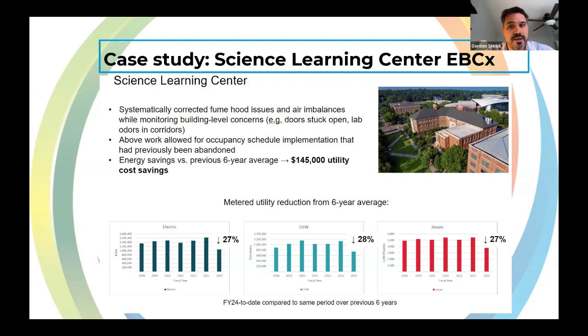And so, we were looking at over 25% energy savings over a 6-year average, which is usually unheard of, but is possible because there's dual parts of significant airflow savings, and also being able to do weekend and evening occupancy schedules. So yeah, I highly recommend that to anyone who's got a building of that similar profile, which is an unusual one. But yeah, we can talk about other buildings which we have, but I'm cautious of time.